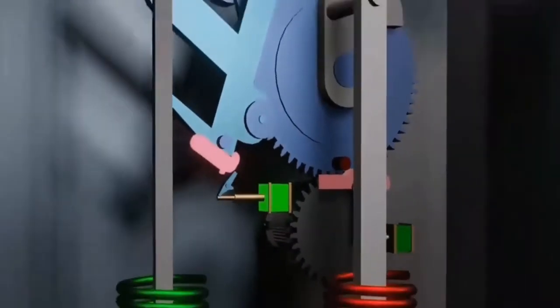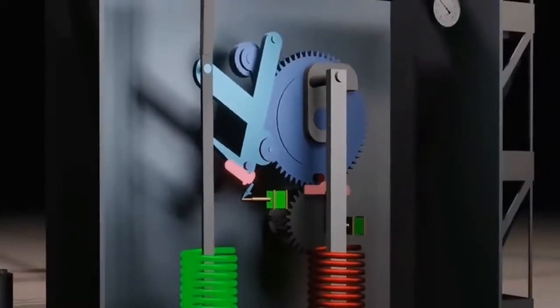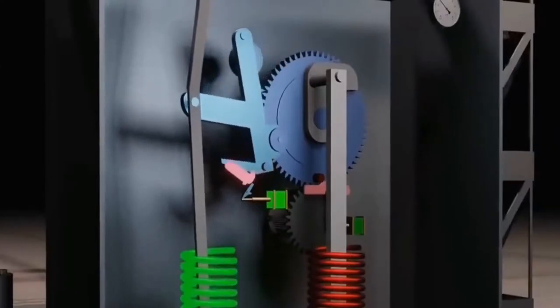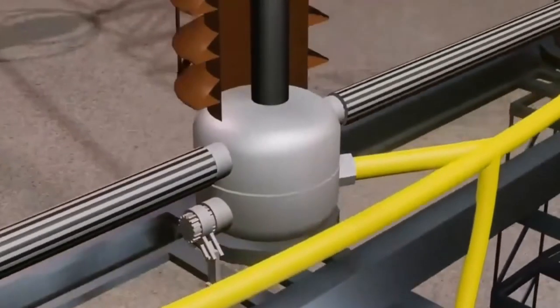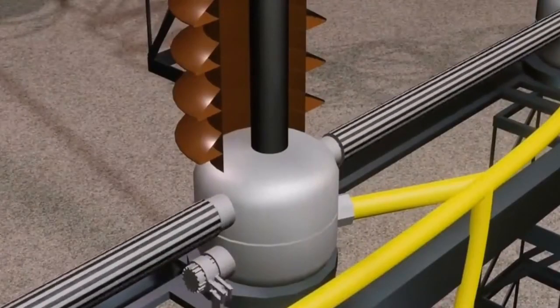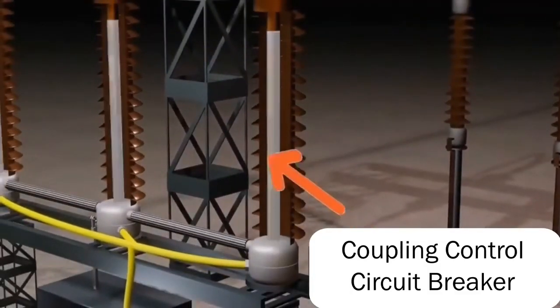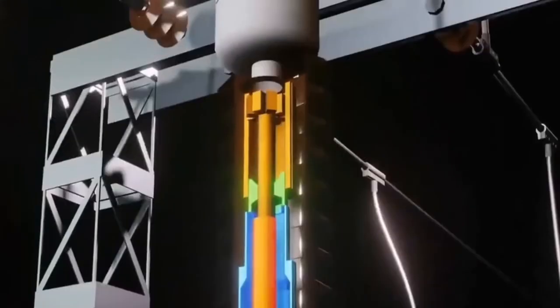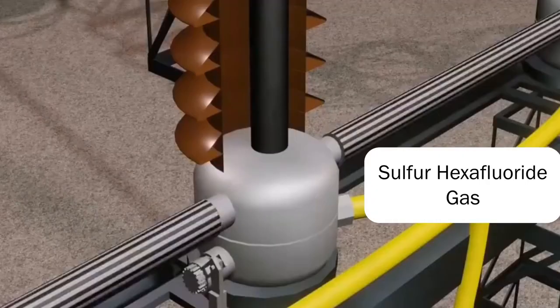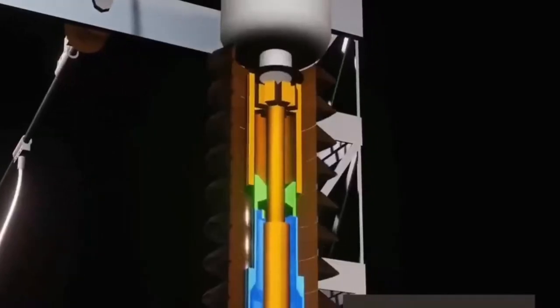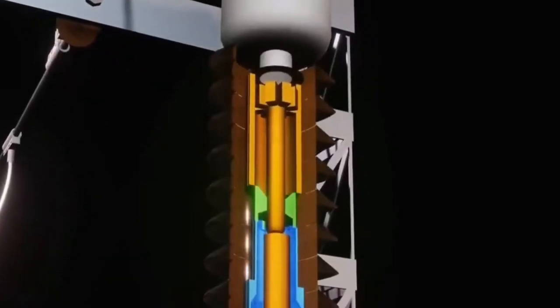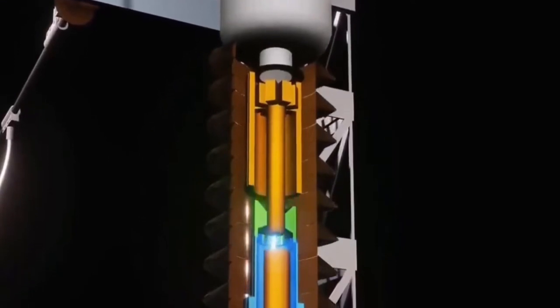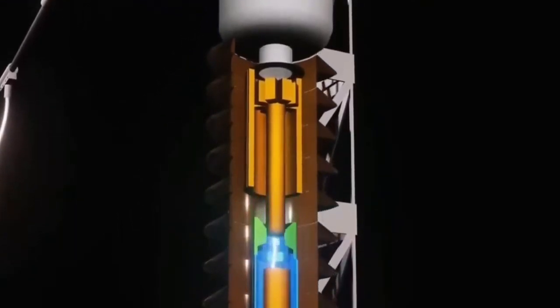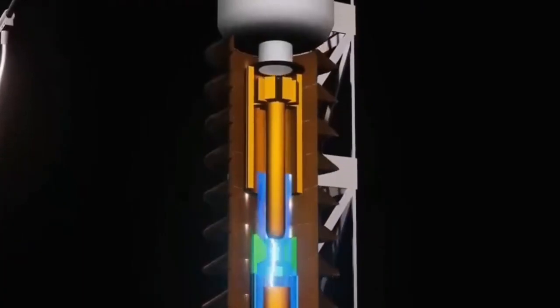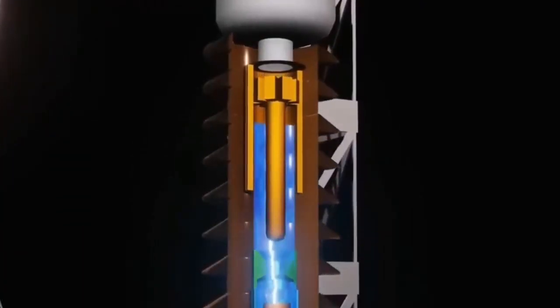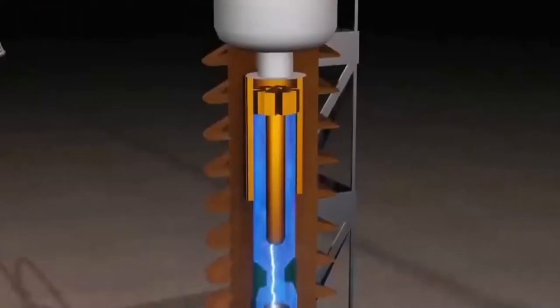At this point, the spring on the left will release its tension, then quickly pull down, connecting to the lever on the spring, which is connected to the small gear at this position, causing the shaft to rotate rapidly, with the shaft simultaneously connected to 3 circuit breakers. Take a closer look at the cylinder of this joint. It is actually filled with sulfur hexafluoride gas, which, when the shaft rotates, will move the lower contact downward, generating a very powerful arc when the upper and lower contacts disconnect as before. Due to the downward movement of the piston, the pressure of sulfur hexafluoride gas increases, causing sulfur hexafluoride to move upwards, completely extinguishing the arc between the 2 contact points.